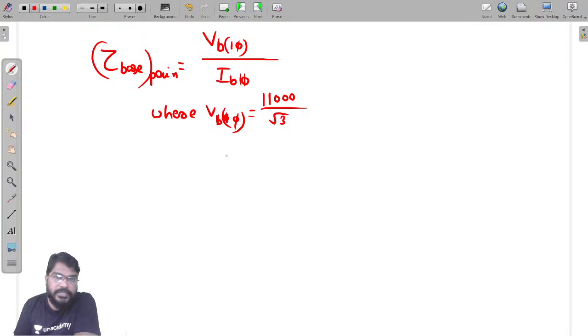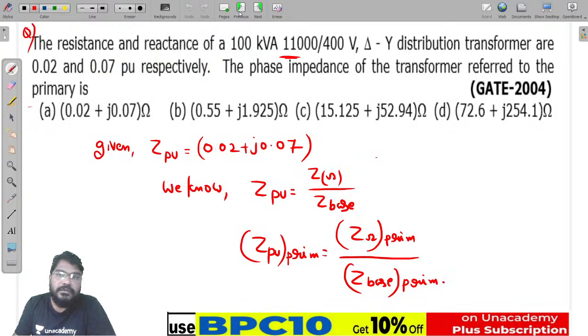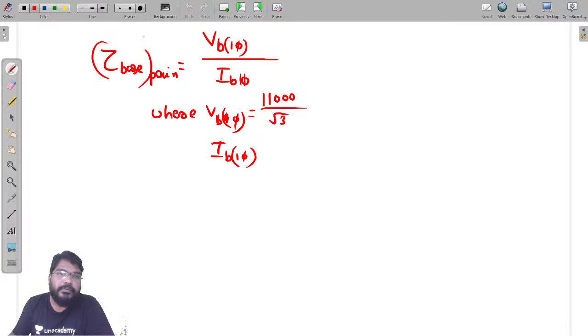Next, IB in the single phase manner. Now, is it delta or star connection? Here the primaries are connected in delta, secondaries are connected in star. So there's no need to multiply by root 3 here.